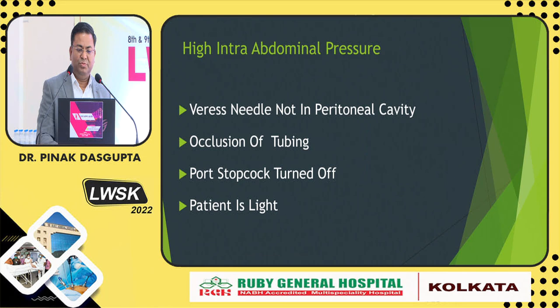These things should be remembered so that as and when a problem comes, we can troubleshoot it. Similarly, if there is a sudden rise in intra-abdominal pressure, we should check whether the Veress needle is inside the peritoneal cavity, whether the tubes are occluded, or whether the stopcock is accidentally turned off. At times, if the patient is light, the pressure will also be high.